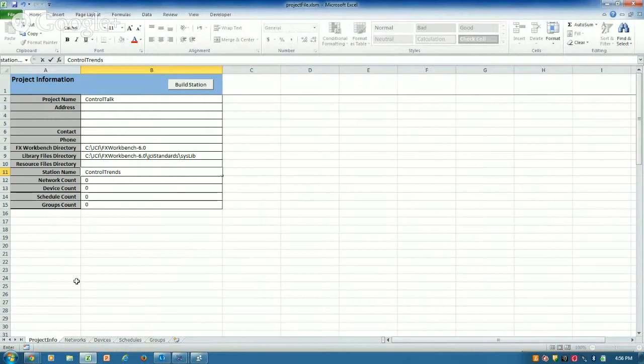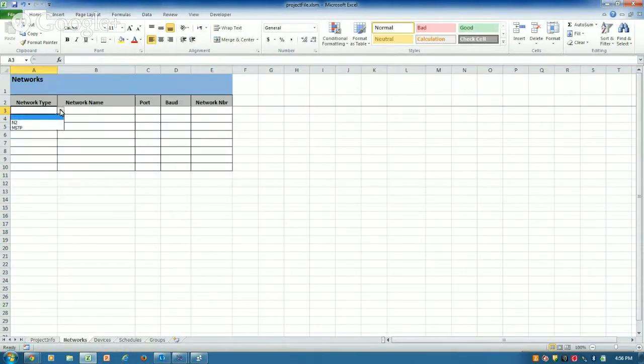Then I navigate using the tabs at the bottom of the screen and add my network. Let's say I add a BACnet network. This automatically adds a BACnet MSTP network, gives it that name, automatically chooses the port, the correct baud rate, and it's up to you to put in your network number. That saves the process of manually configuring the COM port and enabling everything, since it does all that automatically.